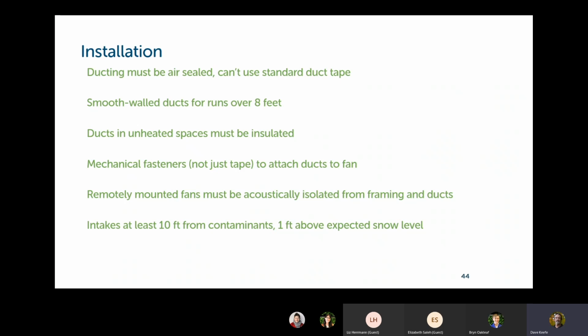Any outdoor intakes you have have to be at least 10 feet from contaminants, so probably the driveway is not a good thing, and at least 1 foot above the expected snow level. Screens, louvers, or grills on intakes and exhaust.